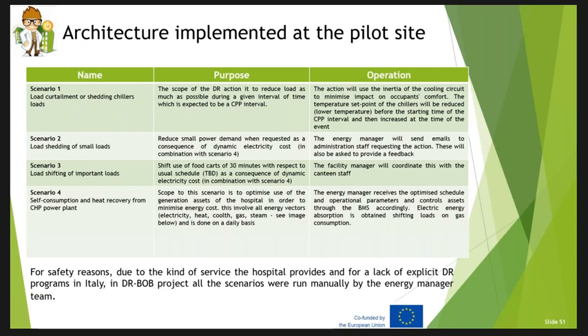Scenario 3 is trying to lower the consumption of important loads, for example, the food carts. The food carts are used at lunchtime to deliver food to the inpatients, and we use them as a thermal storage. We pre-warm or warm the food carts a little bit later, so we can shift the power consumption of those assets by 30 minutes before or after, in order to have an event that lasts 30 minutes.